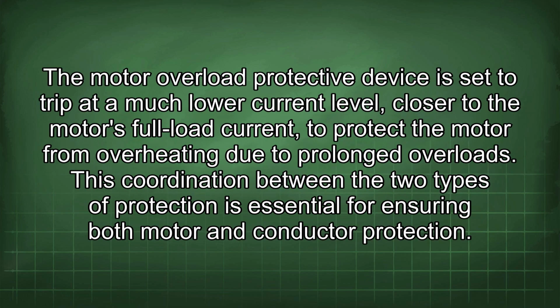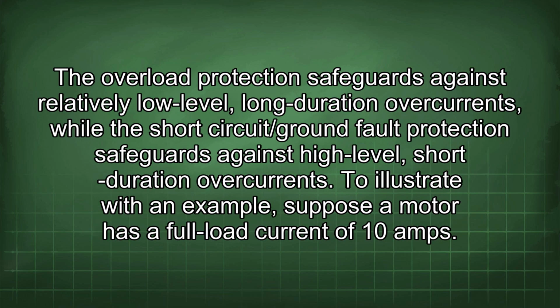The motor overload protective device is set to trip at a much lower current level, closer to the motor's full load current, to protect the motor from overheating due to prolonged overloads. This coordination between the two types of protection is essential for ensuring both motor and conductor protection. The overload protection safeguards against relatively low-level, long-duration overcurrents, while the short circuit/ground fault protection safeguards against high-level, short-duration overcurrents.